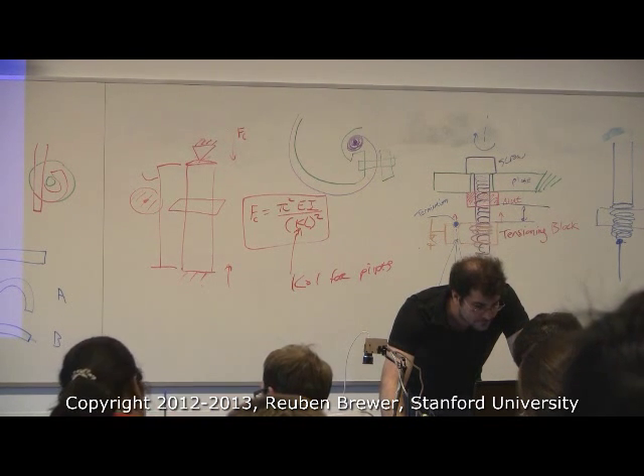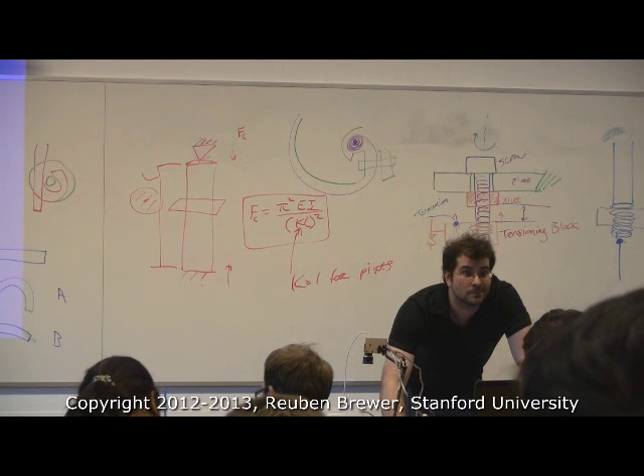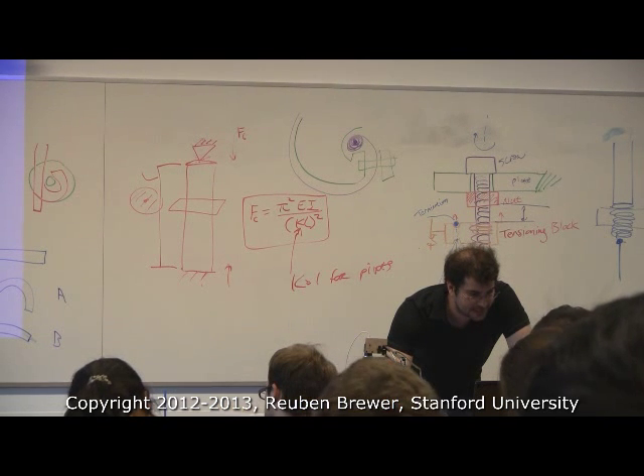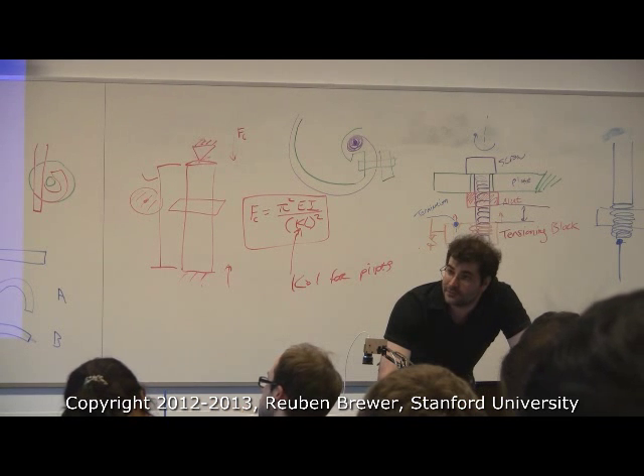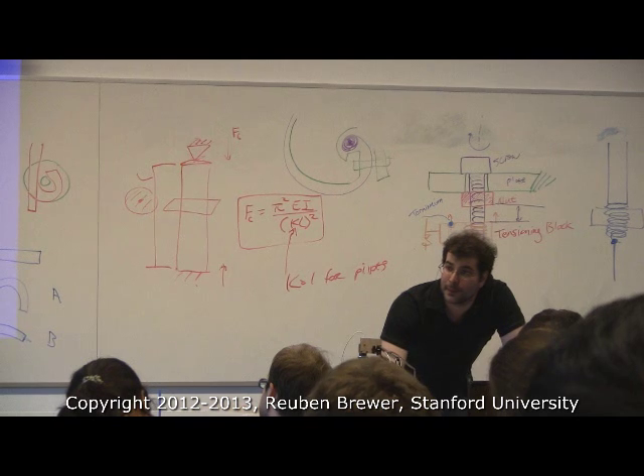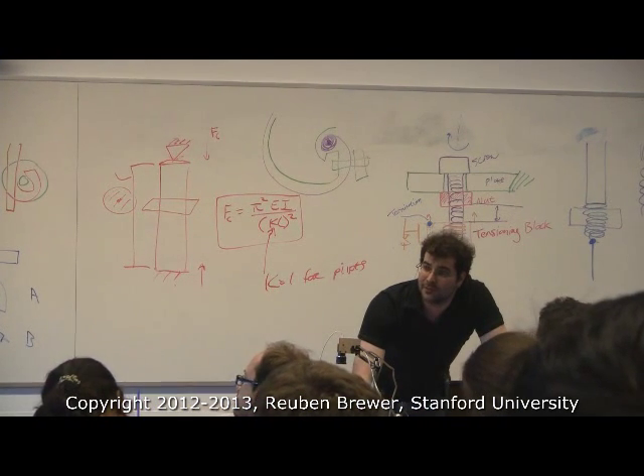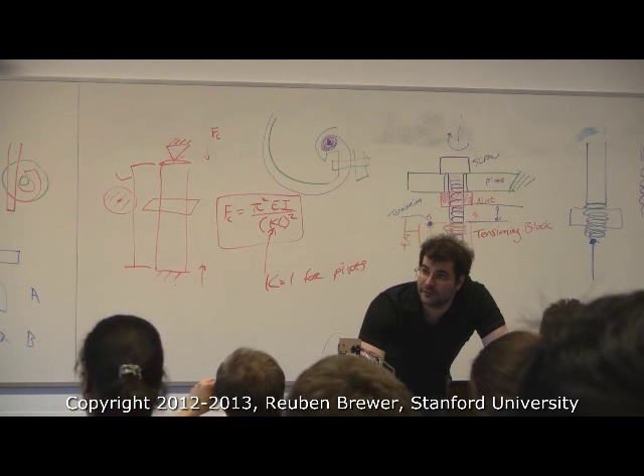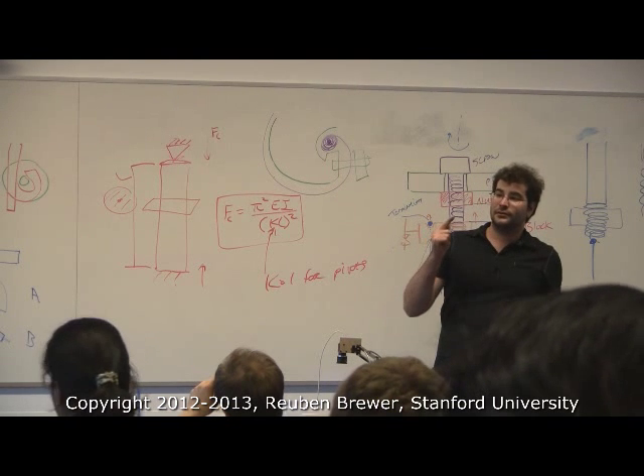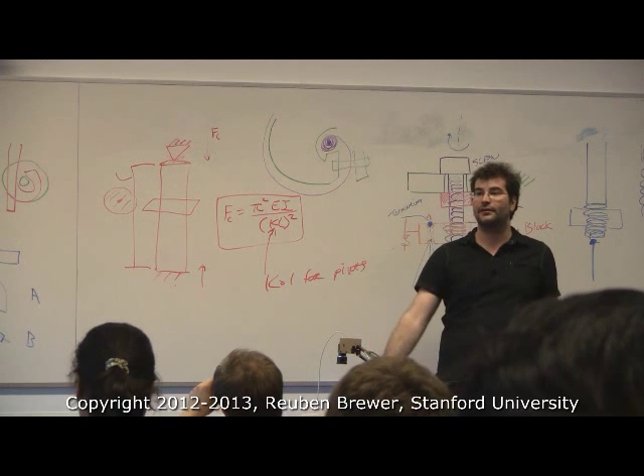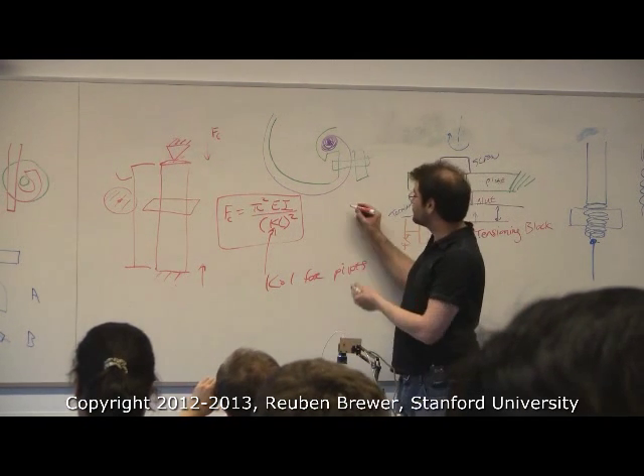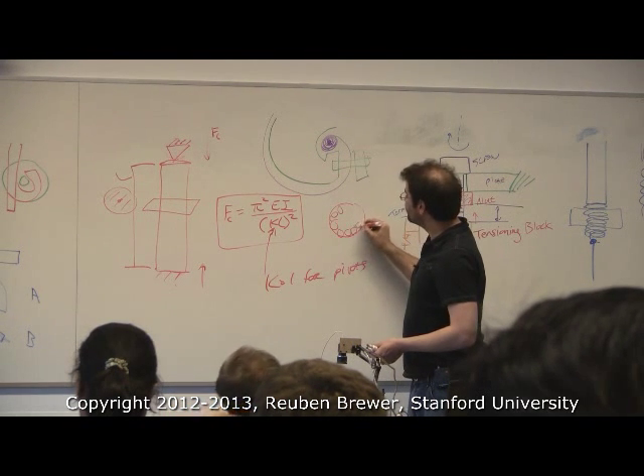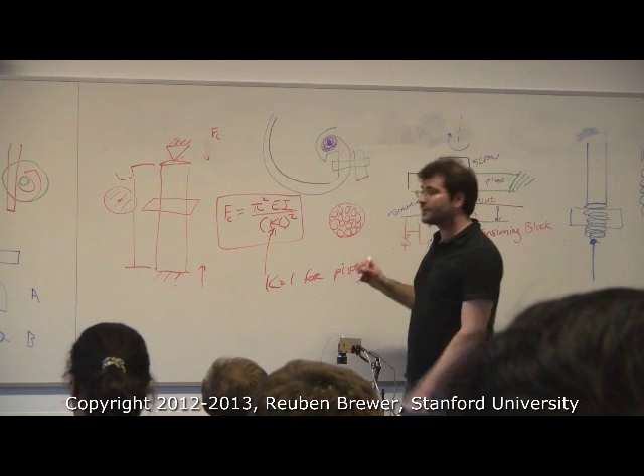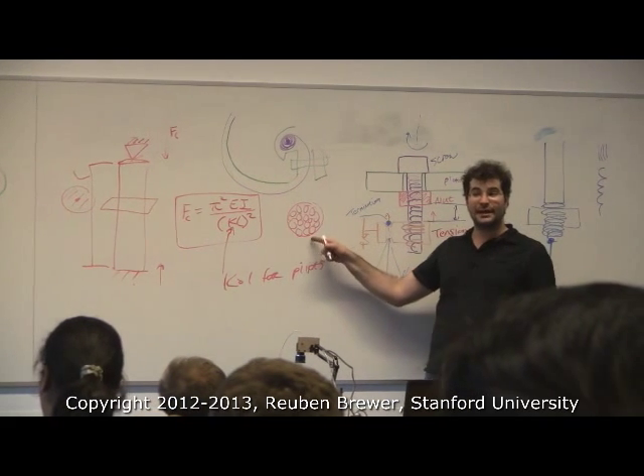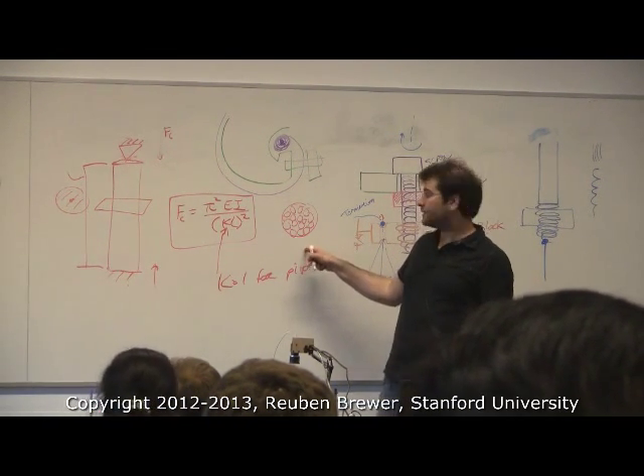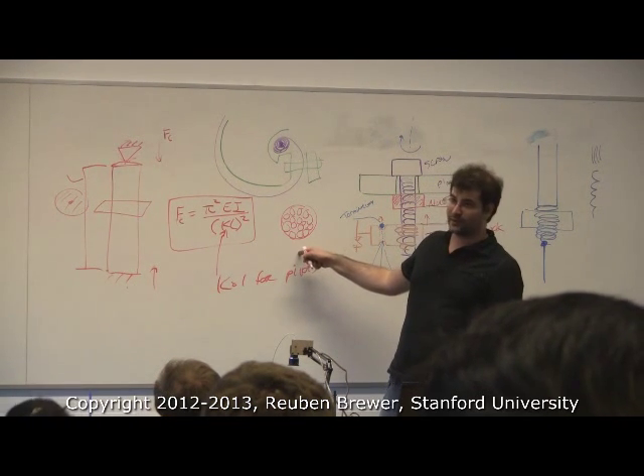Do you want to mention the consequence of bend radius and bend angle? Sure. The exact same minimum bend radius for braided cables applies to nitinol, but it's worse. Anyone know why? Go back to the cable construction we talked about—remember the 7x49? Nitinol is a solid core, not really a fiber, just one single strand. For the same diameter, the steel cable is filled with lots of little strands, each of which is way more flexible and has a much smaller minimum bend radius than the single core. Nitinol gets nasty, even with its super elasticity, in terms of minimum bend radius. Look it up, respect it, otherwise it's going to kink, break, and be bad.